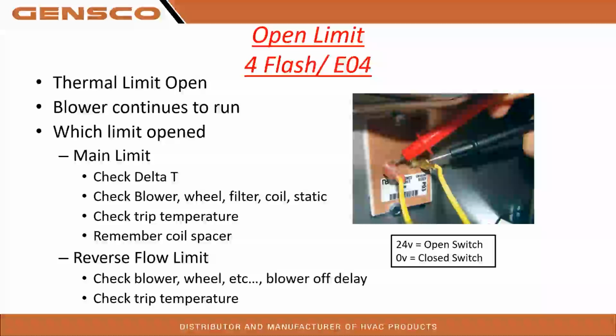So we're going to check delta T. We're going to check the blower, wheel, filter, coil, static, right? We're going to make sure the airflow is doing what it should be doing, that we're moving the air we need to move. Maybe the homeowner had a filter that sucked down on top of the blower motor, something like that. Or we've had some filtration issues in the past, say a 7, 8, 9, 10-year-old furnace with no issues, all of a sudden having limit issues. Could be because some dirt was getting by those very plugged filters. And now we have dirt on the secondary, if it's a 90, or we have dirt on the blower wheel, and we're not scooping the air like we should. So we're going to look at all these things.